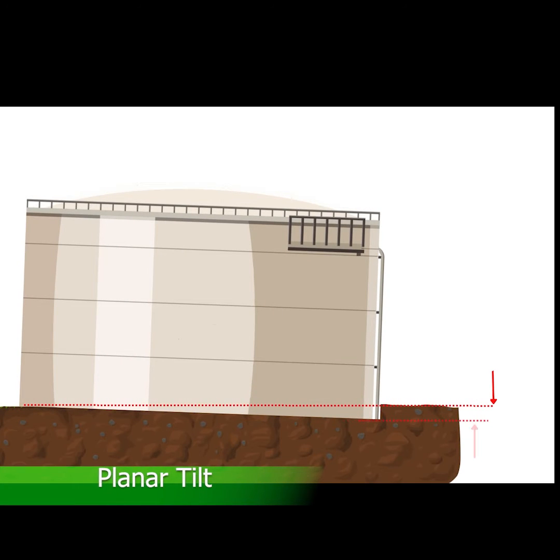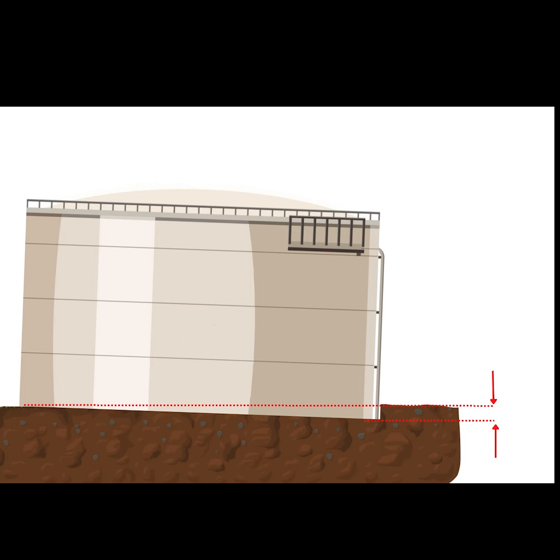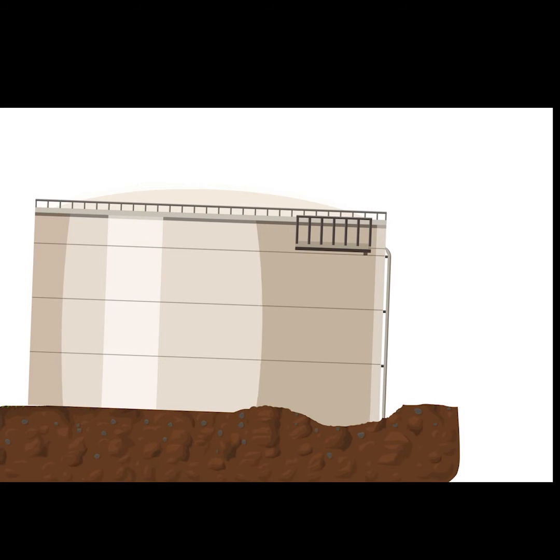Planar tilt. This type of settlement results in increased hoop stress in the tank shell and may cause binding of peripheral seals in a floating roof and inhibit roof travel.